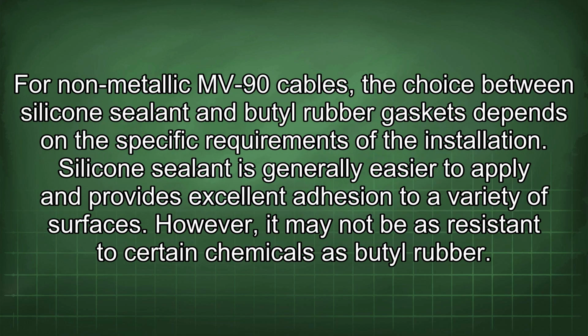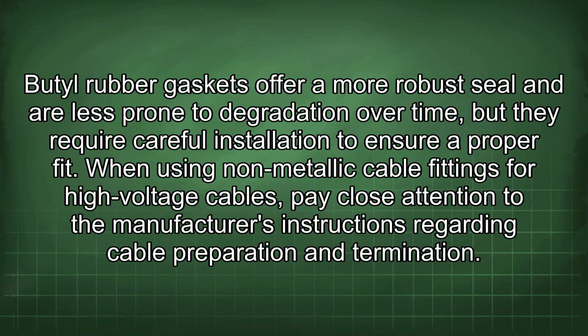For non-metallic MV-90 cables, the choice between silicone sealant and butyl rubber gaskets depends on the specific requirements of the installation. Silicone sealant is generally easier to apply and provides excellent adhesion to a variety of surfaces. However, it may not be as resistant to certain chemicals as butyl rubber. Butyl rubber gaskets offer a more robust seal and are less prone to degradation over time, but they require careful installation to ensure a proper fit.